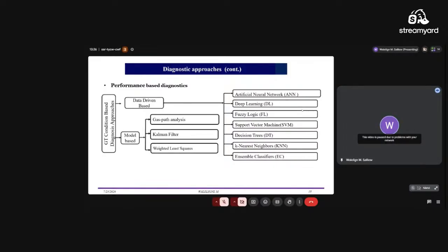So we have two approaches of developing a diagnostics model. The first one is model-based. In gas turbine, we call it a 1D performance model. You know, just calculating the gas turbine performance at each stage: compressor exit, turbine exit, combustion chamber exit. So we have a baseline. When it deviates from that baseline, that means there is a fault. So that's model-based. It uses the thermodynamic equations.